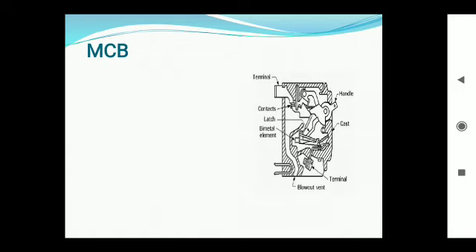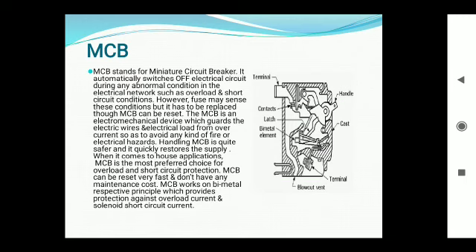Now this is the image of a MCB. These are the various parts of the MCB: handle, cast, terminal, blowout vent, bimetal element, contact latch. So MCB stands for miniature circuit breaker. It automatically switches off the electrical circuit during an abnormal condition in the electrical network, such as overload or short circuit condition. However, a fuse may sense this condition, but it has to be replaced, though an MCB can be reset.